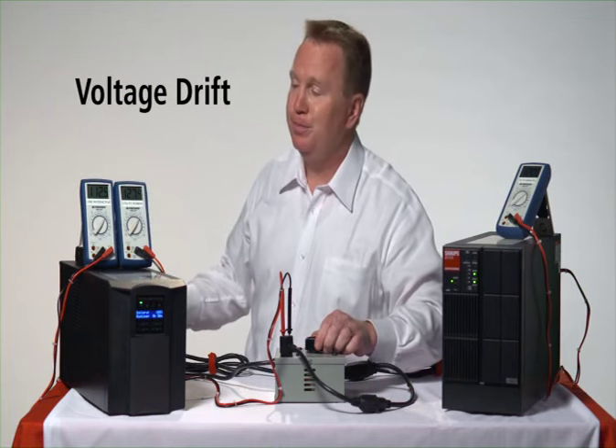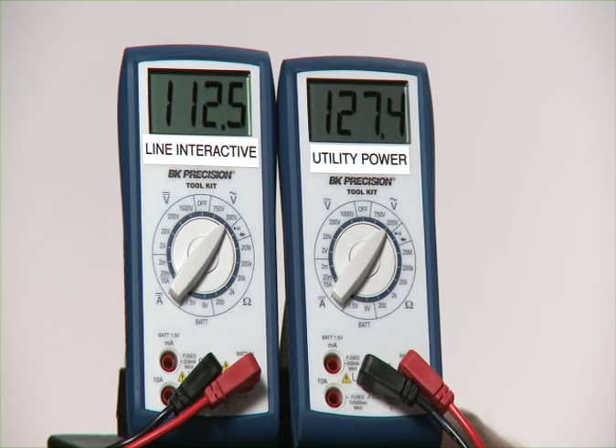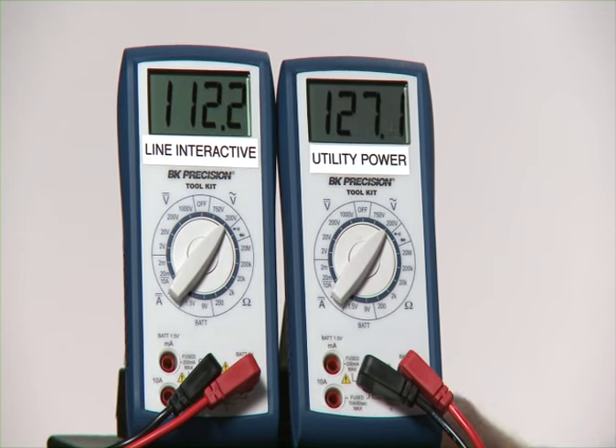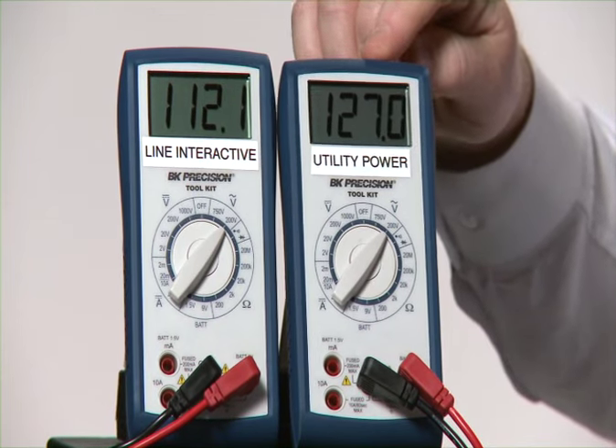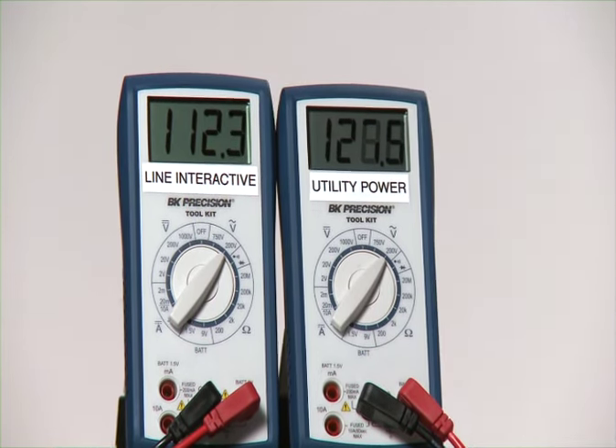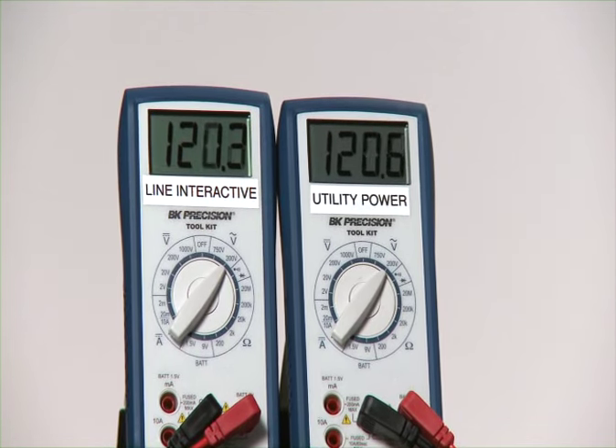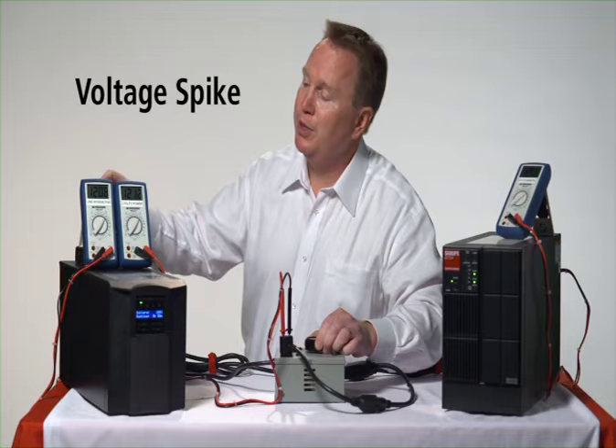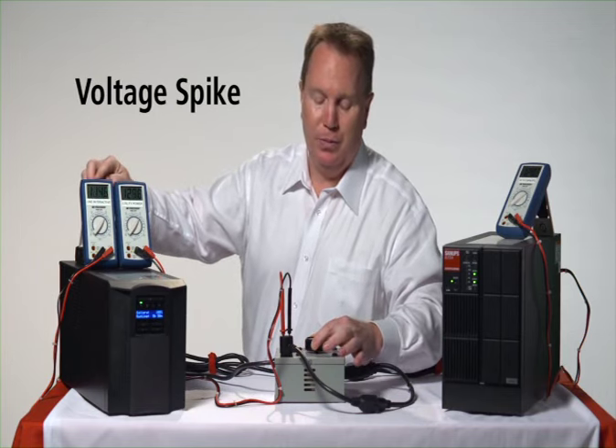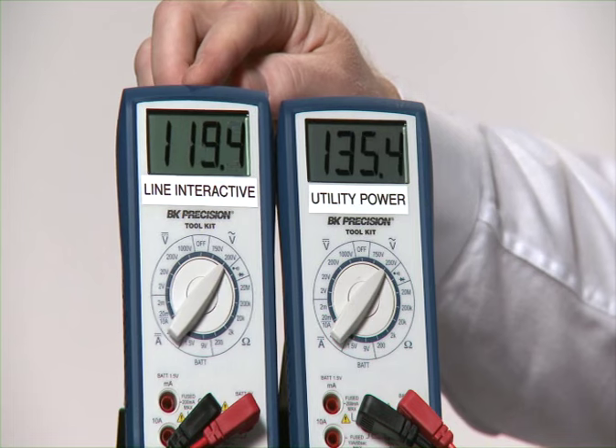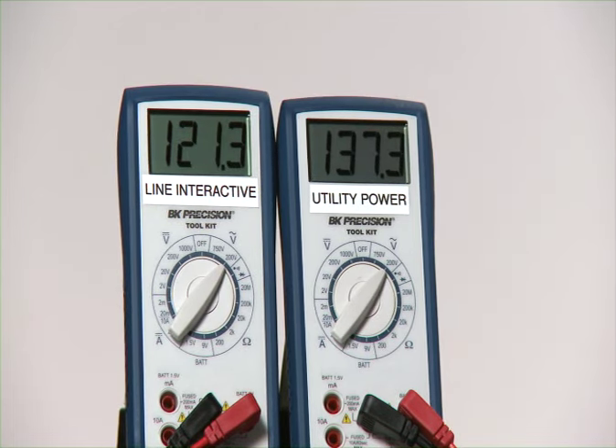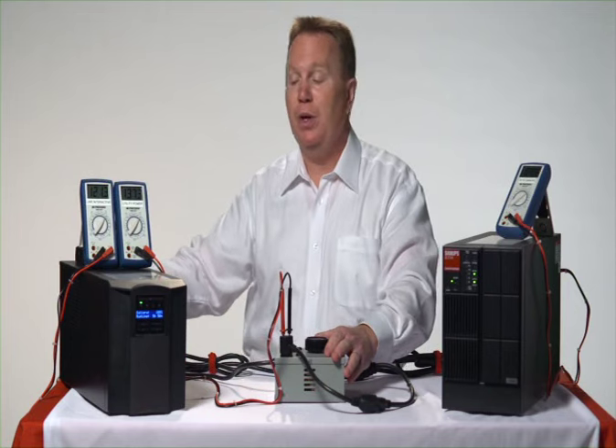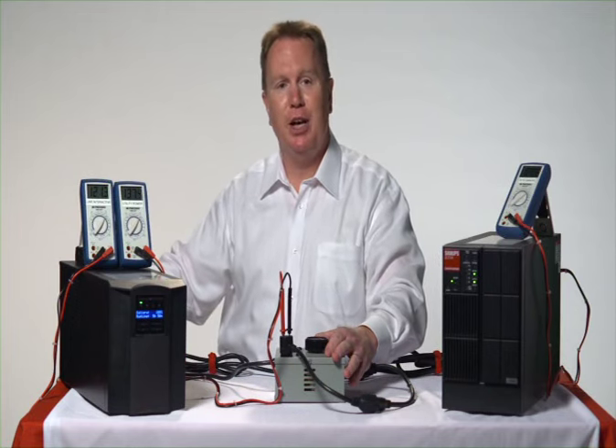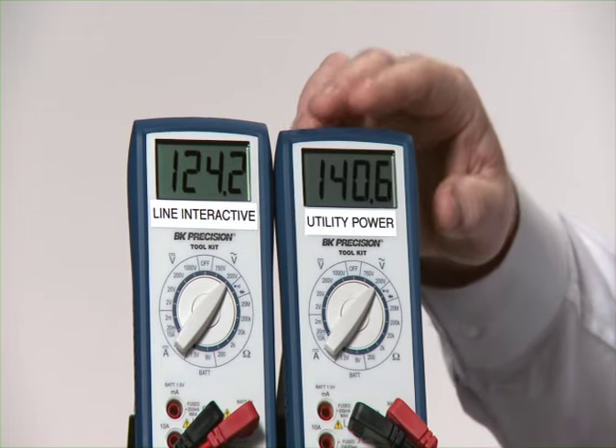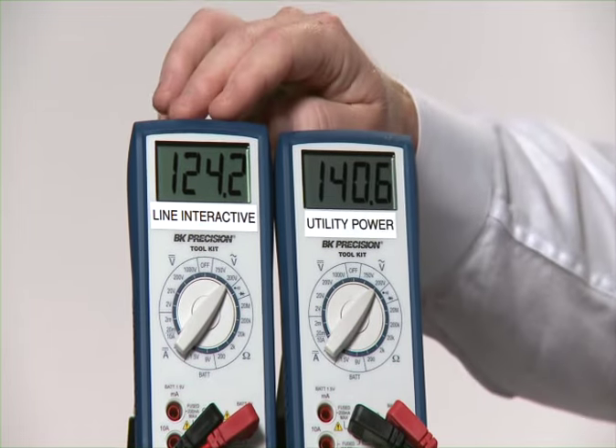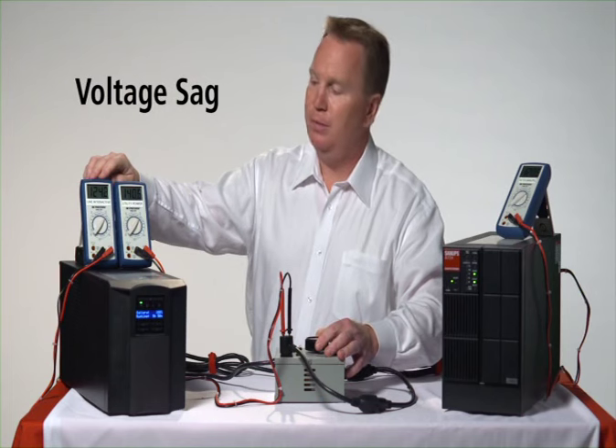Let's go into a drift. One of the most common characteristics of line interactive UPS is the one-to-one relationship of utility voltage or input voltage to output voltage. In this drift demonstration, as input voltage changes, so does your output. Let's proceed up to a spike. As we climb, you're going to hear a click. What just happened is an automatic voltage regulator has kicked in. It's the best this unit can do to maintain output power quality. So here we are at 140 volts. Our output is at 124 volts. Let's continue on down.